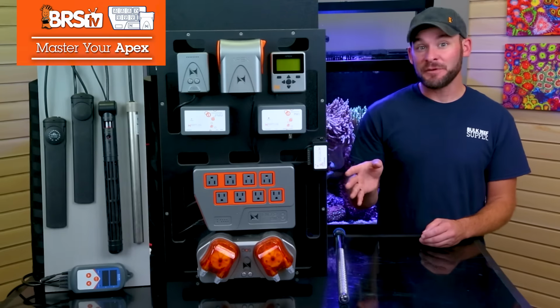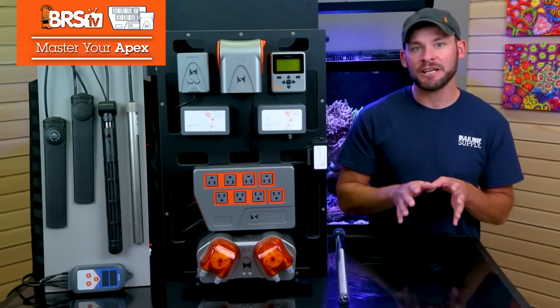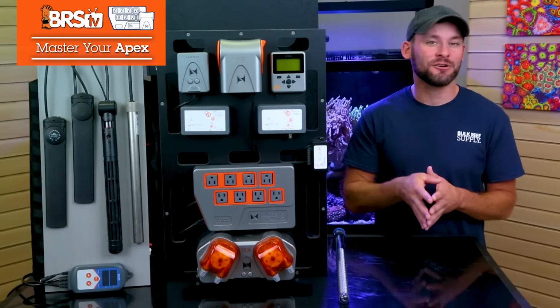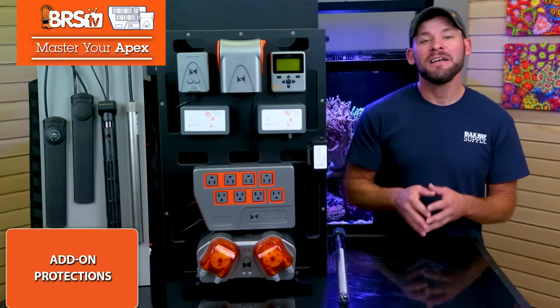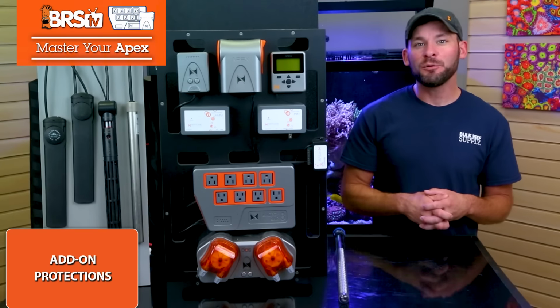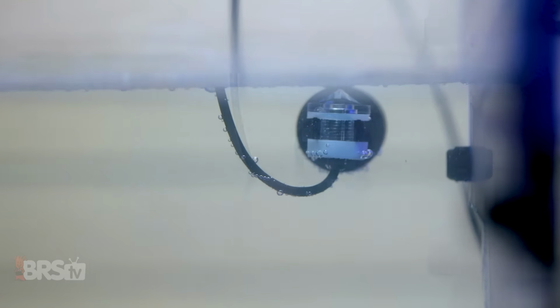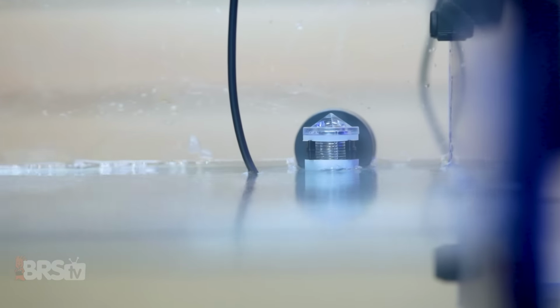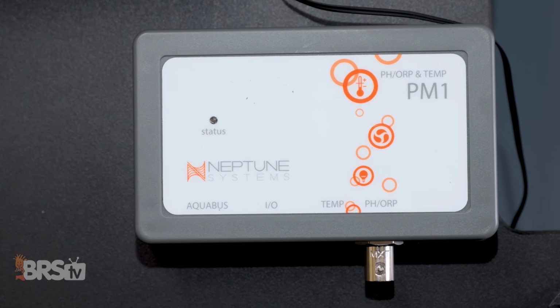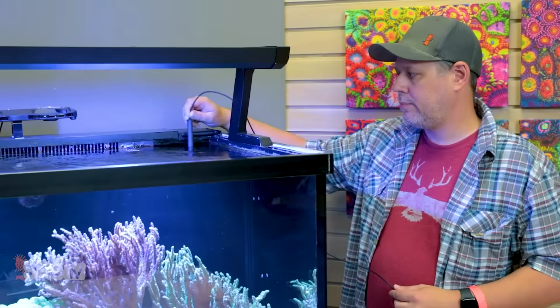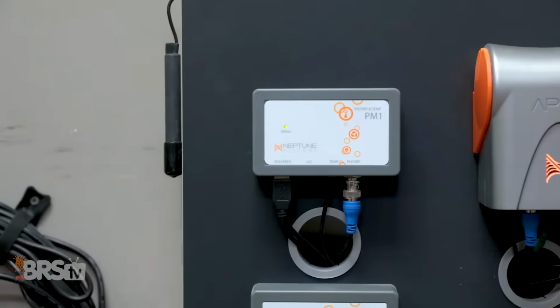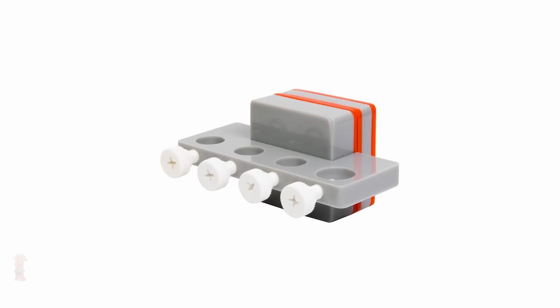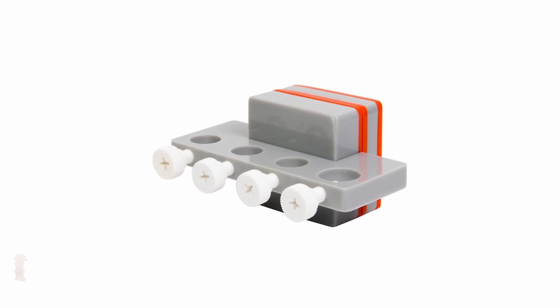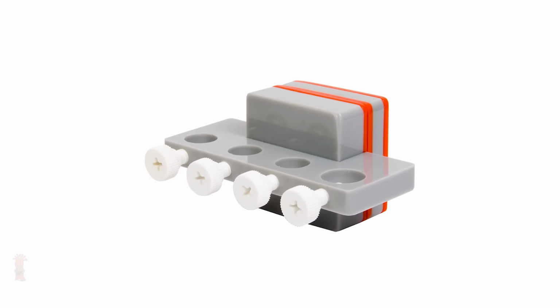Outside of the Apex task functions to protect against heater-related issues, I've got 3 additional Apex accessories and add-ons that we can also implement to help put heater-related worries to bed. Those being an optical sensor to turn your heater off before it gets exposed to air, a PM1 or PM2 module for additional temp probes to monitor the tank or the ambient room temp, and a magnetic probe rack, which is far safer and more reliable than letting your probe dangle in the sump.